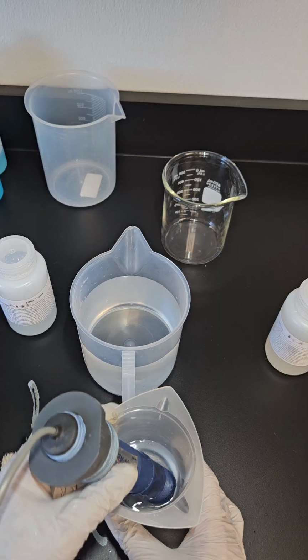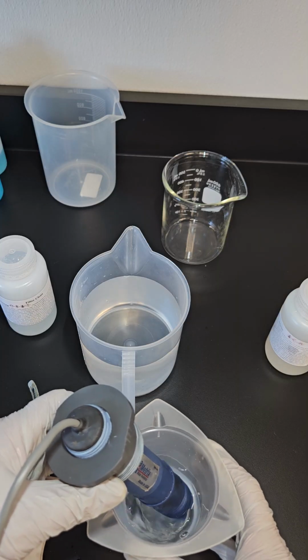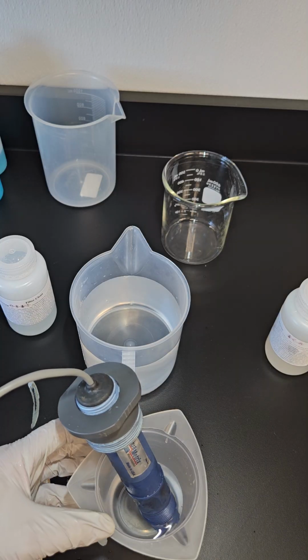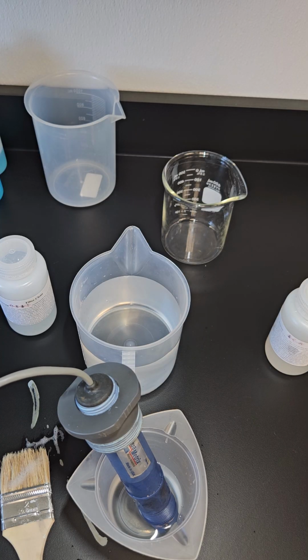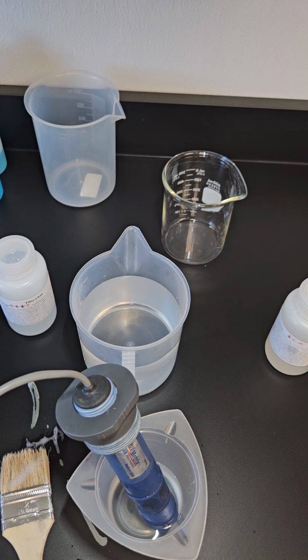Putting this in there, take your timer out and leave it for a good 5 minutes for that acid to work on the probe. It'll take off a lot of the lime scale that builds up on the bulb and make the reaction time much faster. It'll get it thoroughly cleaned off with the acid treatment. Usually only 5 to 7 minutes is necessary, depending. But you don't see the buildup of scale on the bulb with the human eye. Usually you can't really see it. Some places I do actually see the buildup when it's really, really bad. It's really cloudy looking on the bulb.